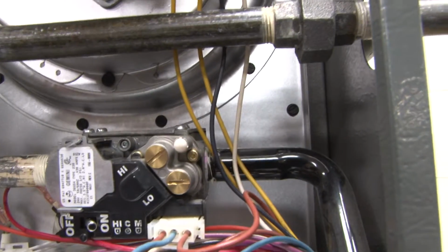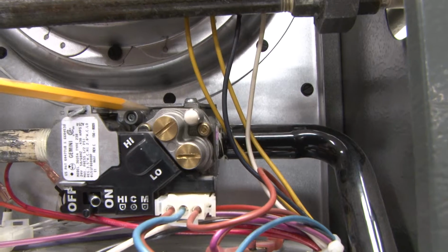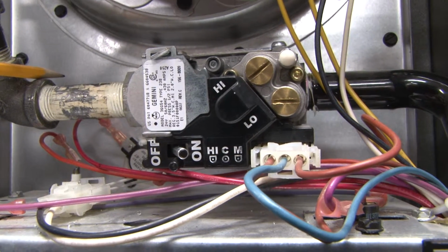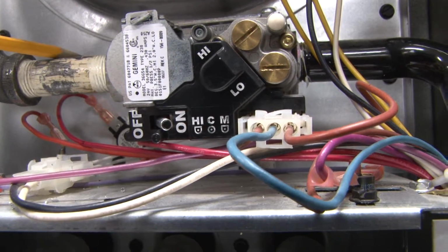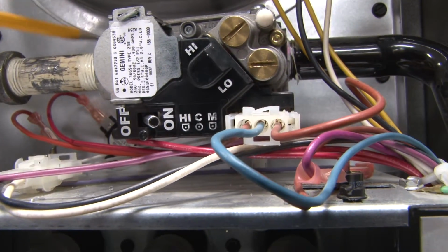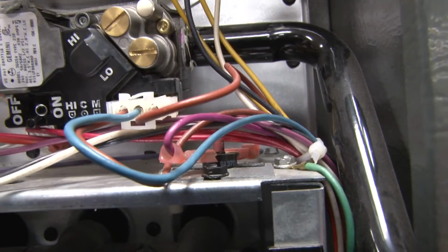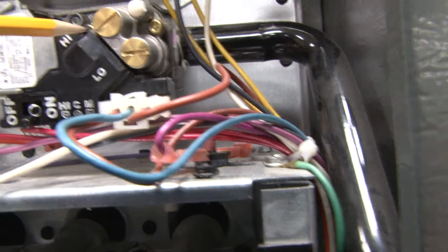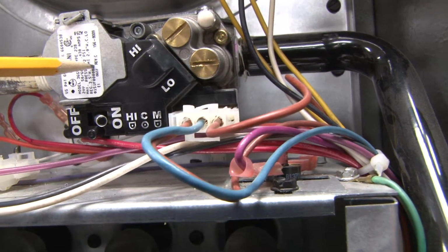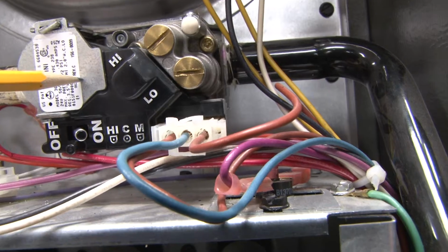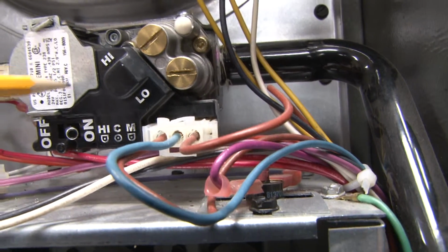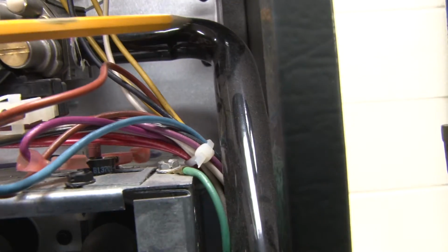We know that the gas valve will allow the gas pressure, the inlet gas pressure, to drop down from about 7 inches, and sometimes it'll be higher, down to 3.5 inches on the outlet of the gas valve. This is a combination gas valve, and it has a built-in regulator and a solenoid to control the gas flow. So it will regulate the pressure down to 3.5 inches through this manifold pressure.